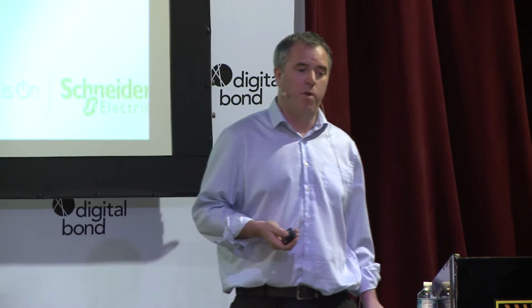But the other important thing from TLS is we get cryptographic agility. So we all know that the algorithms improve over time, the attacks improve over time. TLS has a built-in mechanism of cipher suites where the two endpoints negotiate what security algorithms they want to use, what key sizes they want to use. And these algorithms can actually change without changing the underlying protocol. So by using TLS for Secure Modbus, we get that level of flexibility and future-proofing.